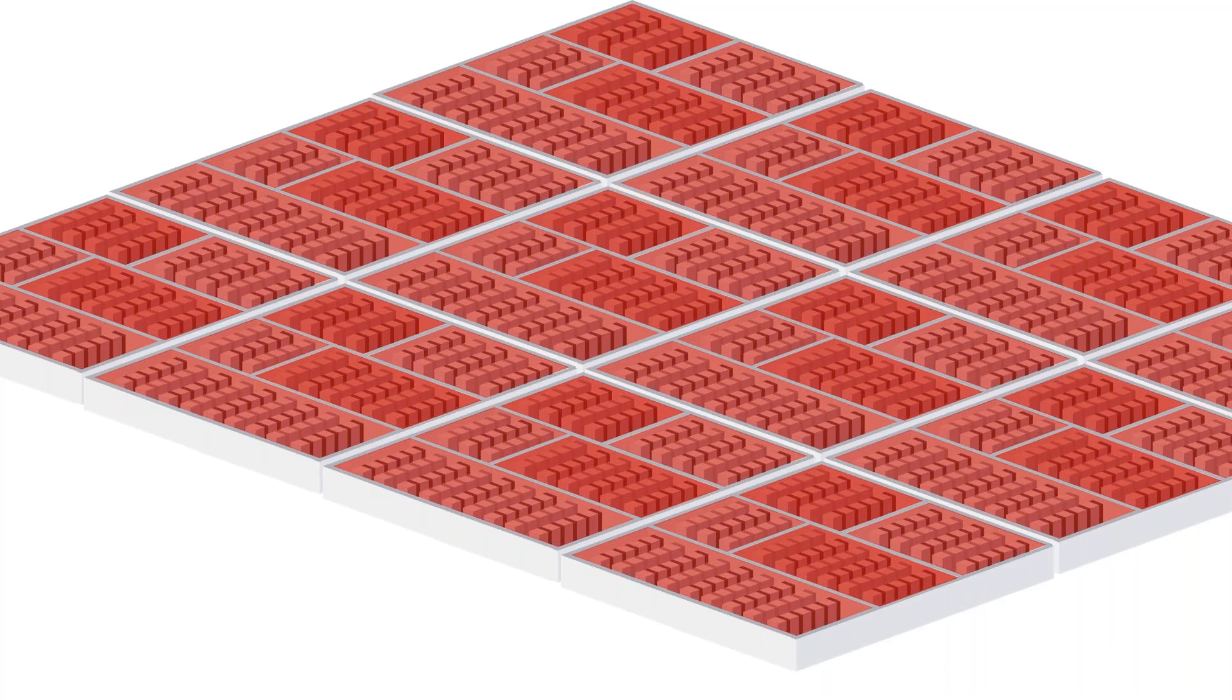You might be sitting there saying I don't know that I need this much valve to control a single whatever, but you're never doing one. The scope of what we're doing makes it invaluable that none of the rest of these racks is going to control the flow to the one you're interested in, because they're hydronically independent of one another. We can read the flow rates of every single valve in this building and write alarms if they're off from what they're supposed to be. And we can sit at a terminal and reprogram every single one of these to whatever flow we want should that need arise. The reality is the EPIV is revolutionizing data center cooling and we're really excited about this product and how it can help you.